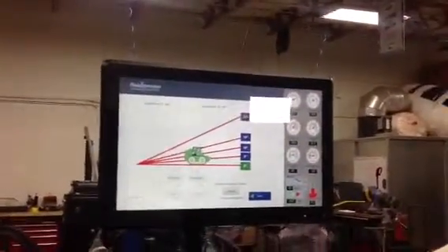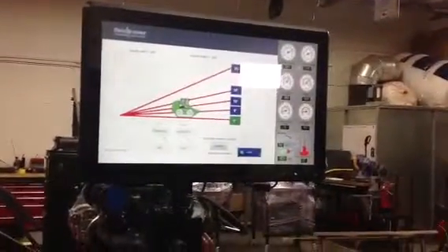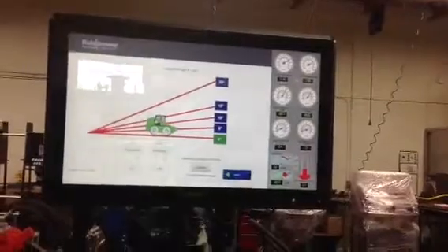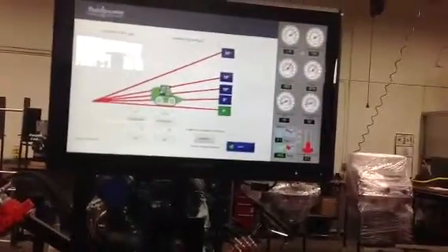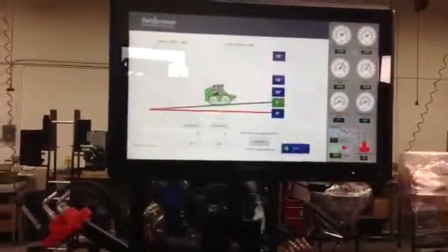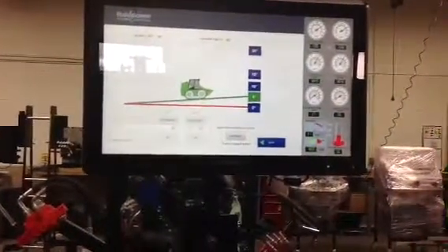Let's say I want the student to learn how to troubleshoot this motor or that pump, to do a flow test on it. I put the flow meter in line, and then I say, let's do this test at 1200 psi. I select 5 degrees. That may take me to 1200 psi. So now this thing is loading to 1200.